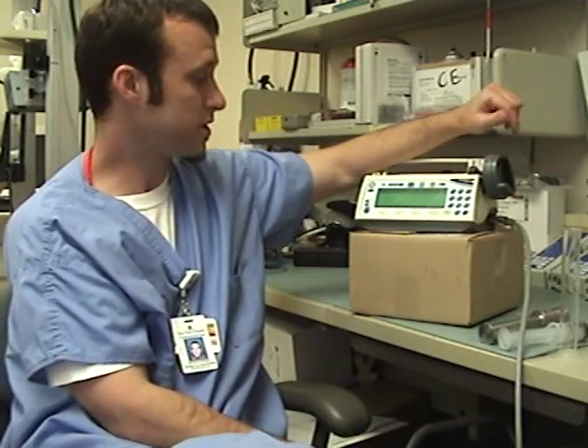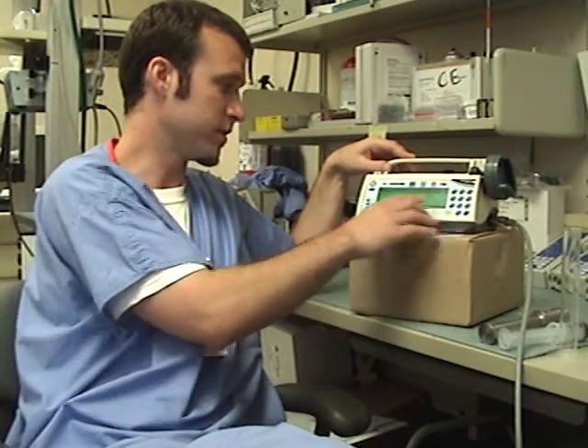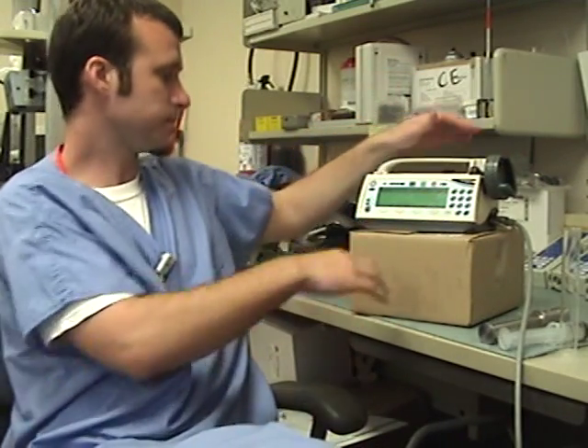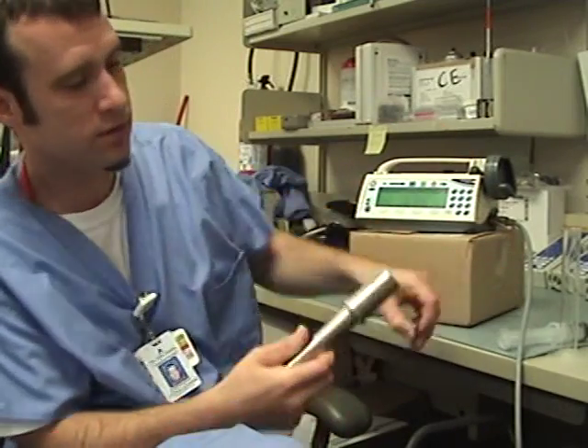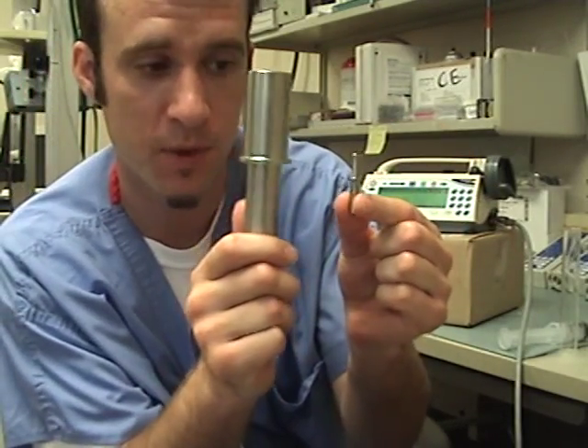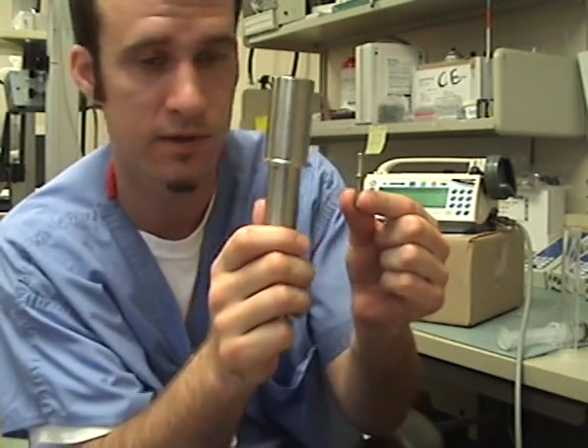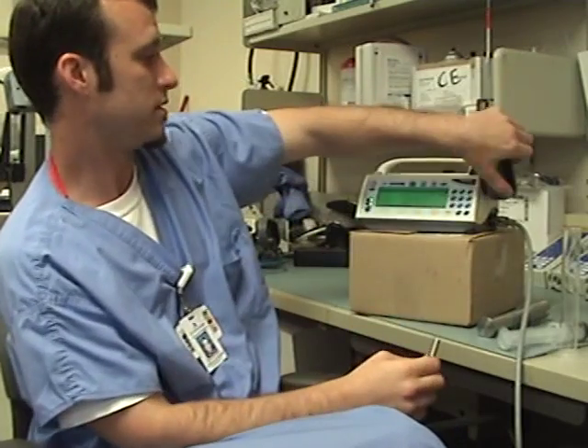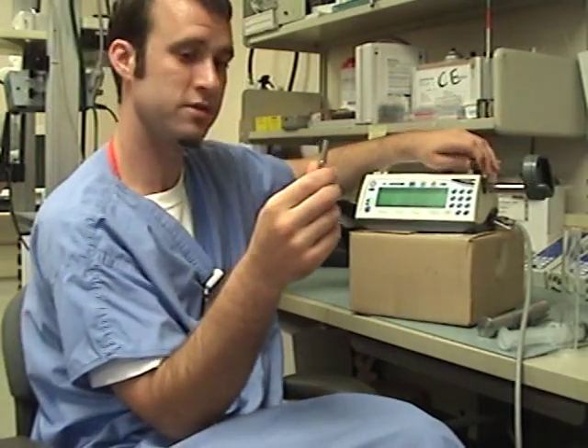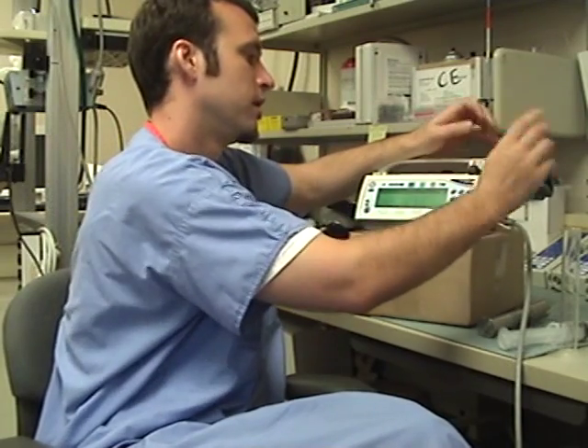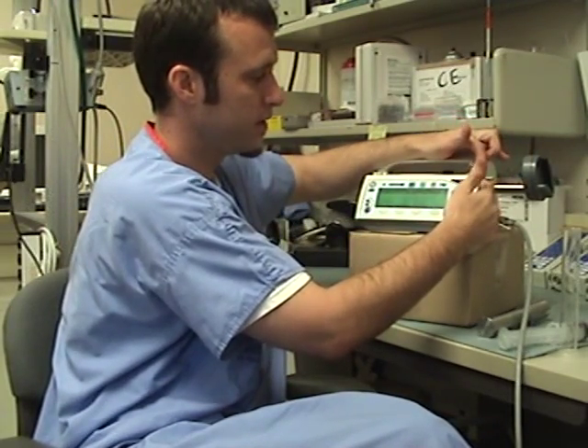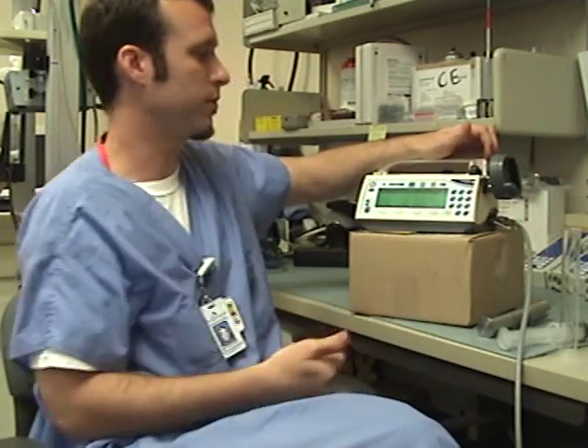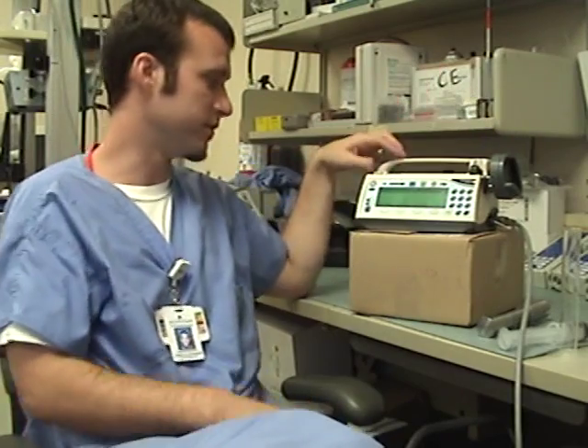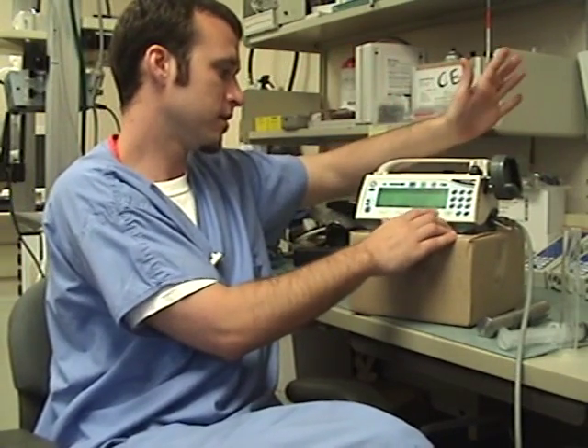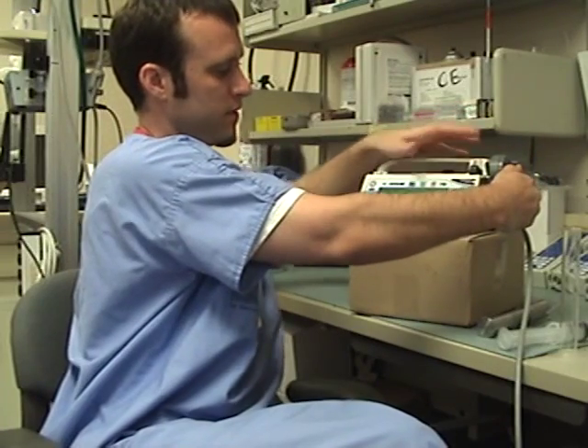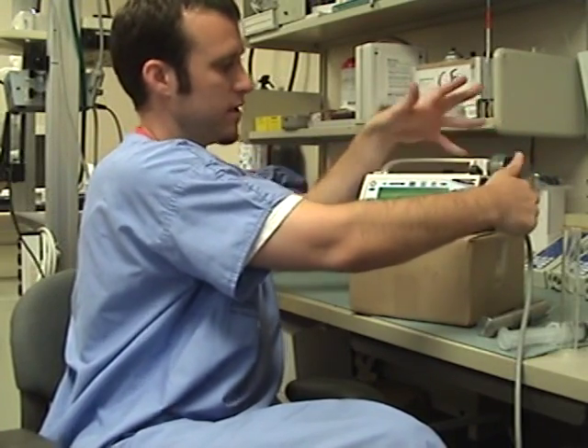Next thing you want to do is go in and calibrate the force, size, and position for the syringe sensors. To do this, you will need two calibrated force or size and position cylinders from the manufacturer. It starts by setting at the low standard, which requires you to use the small calibration plug. Make sure that the lip of this is inside of the syringe holder there. Make sure that the barrels are opened and then closed so that both levers are on top of your device. Set it, hit continue, open your plunger levers, press it up against the unit and hit continue again.